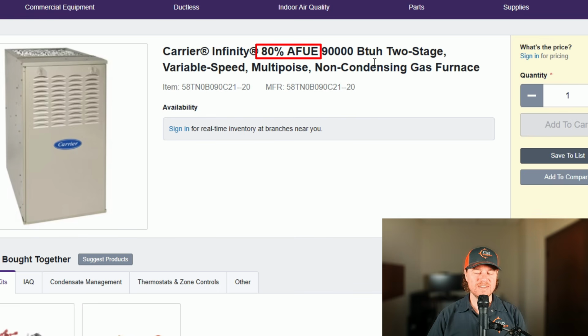The AFUE is 80% efficiency, and for a 4 to 5 ton setup, we would use this 90,000 BTU furnace. And you can see here that it's saying that it's a 2-stage furnace, but right underneath it, it's saying variable speed. So which is it? What's going on here is that it is fully variable in cooling mode, but in heating mode, it has 2 stages that it operates in.